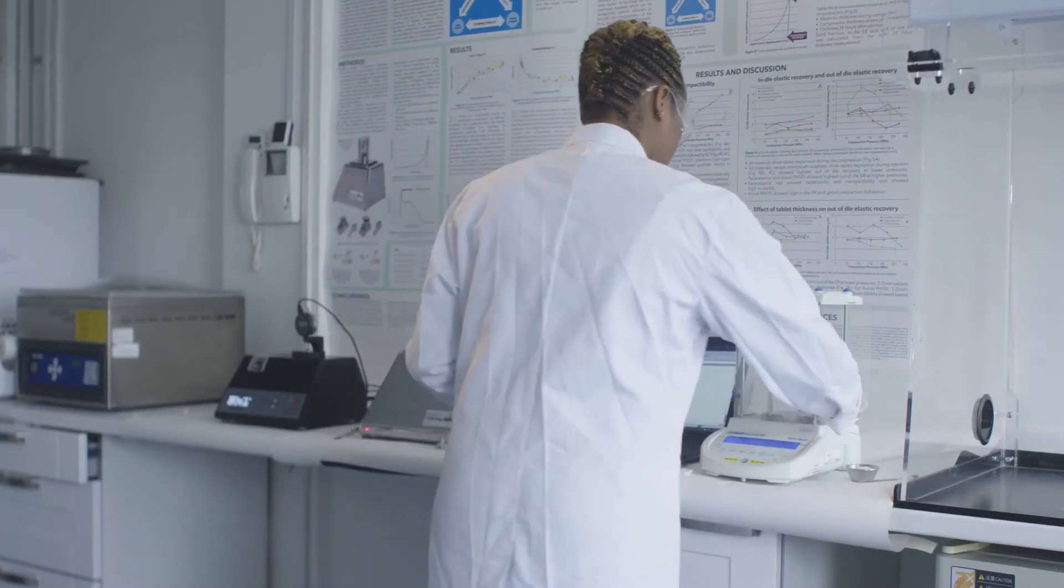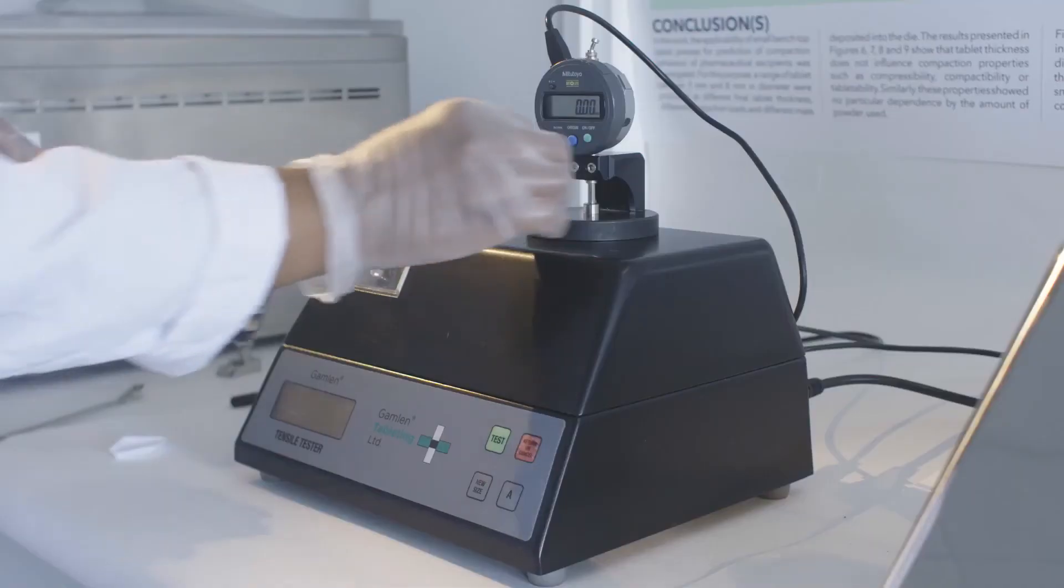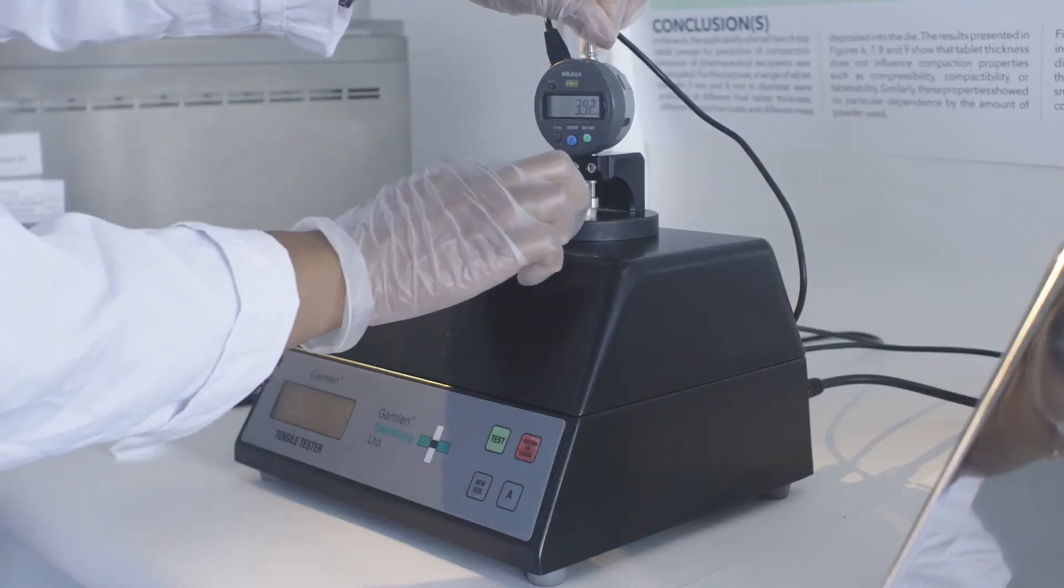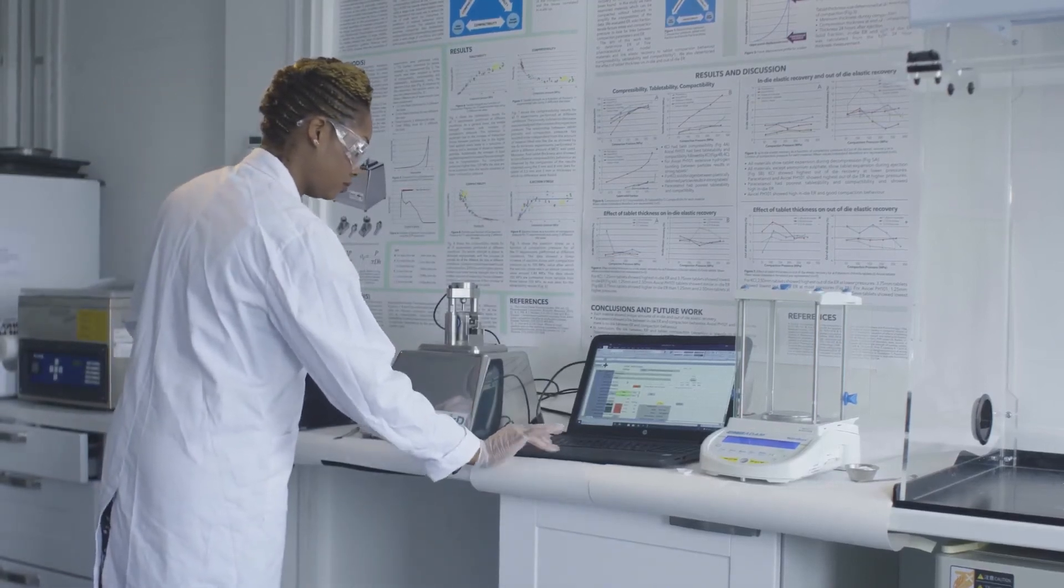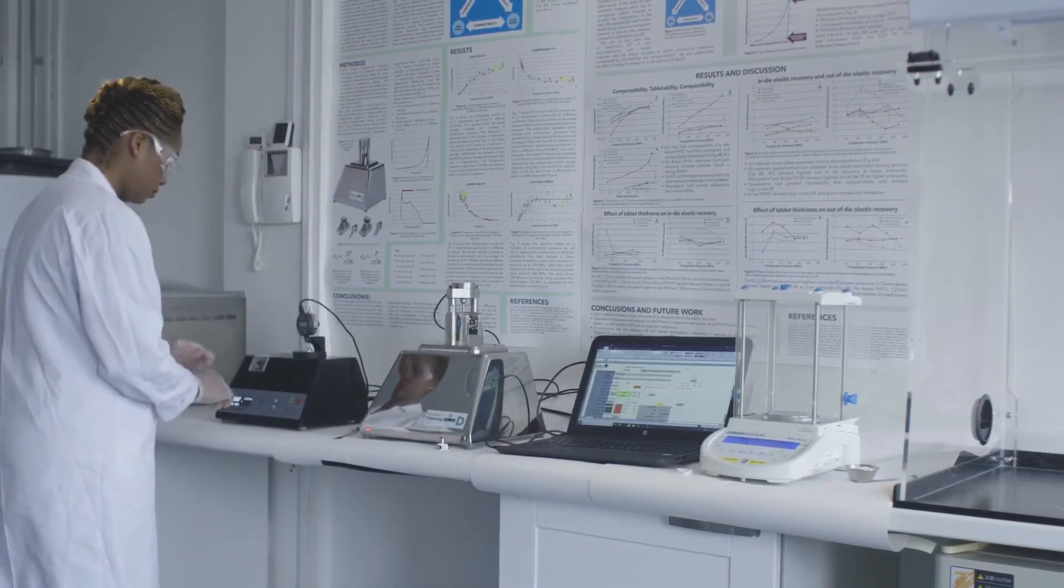The system performs tablet fracture testing and measurement of tablet dimensions. Taken together, these data are automatically analysed and displayed in real time by the user-friendly Gamlen dashboard software.